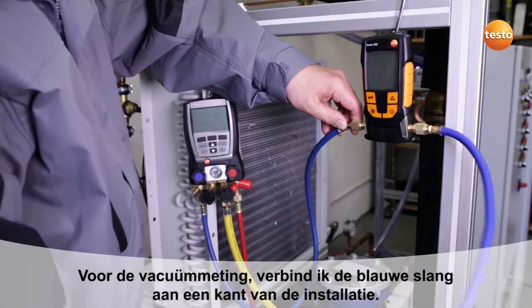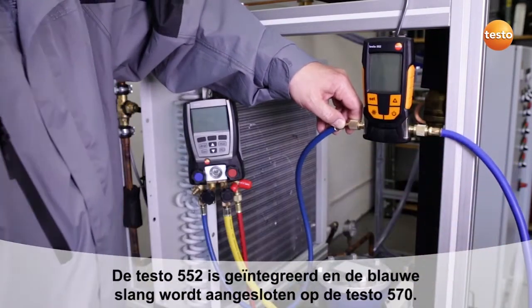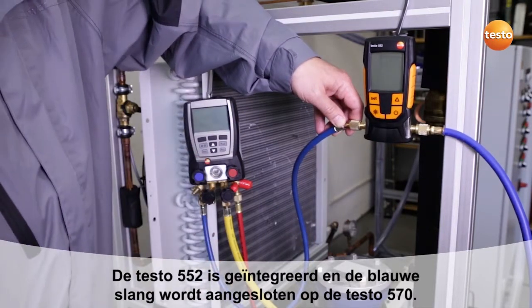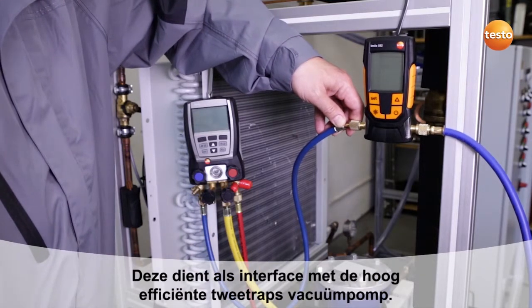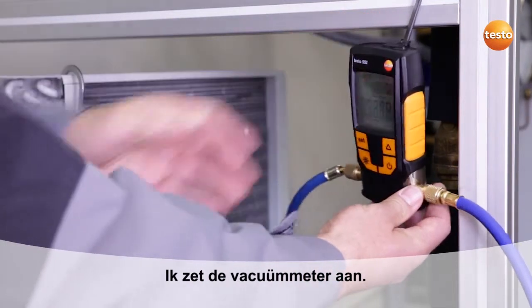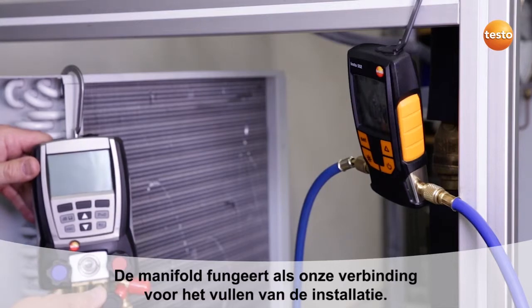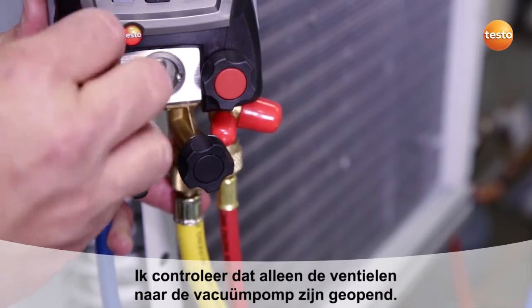I have now connected the blue hose to the plant for the purpose of evacuating one side of the system. The Testo 552 is integrated, and the blue hose ends at the Testo 570, which is the interface to our highly efficient two-stage vacuum pump, which will secure the evacuation procedure. The manifold acts as our connection for filling the system. I am now checking that only the valves to the vacuum pump are opened.